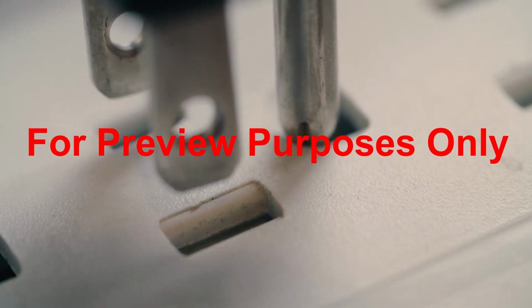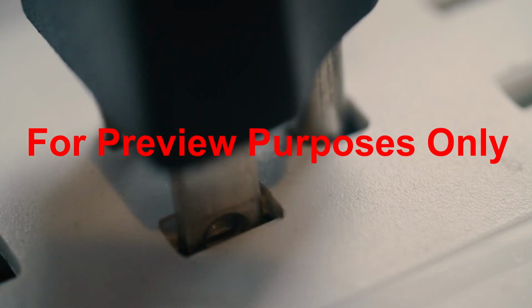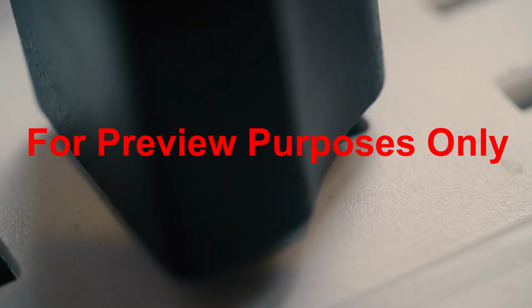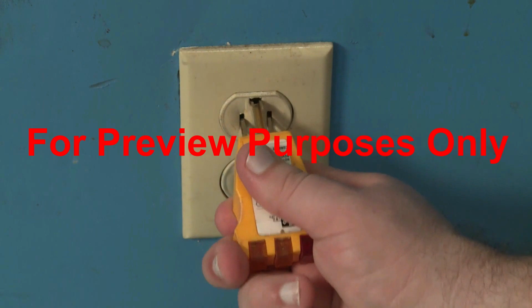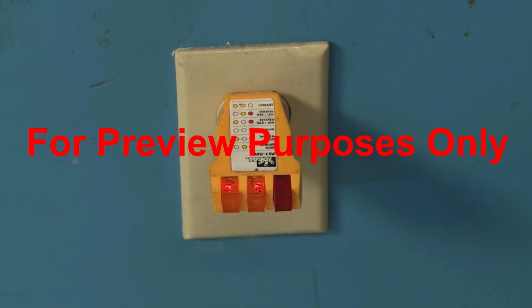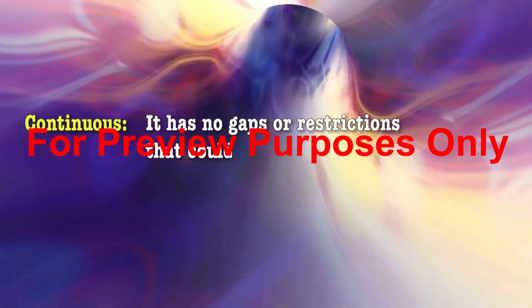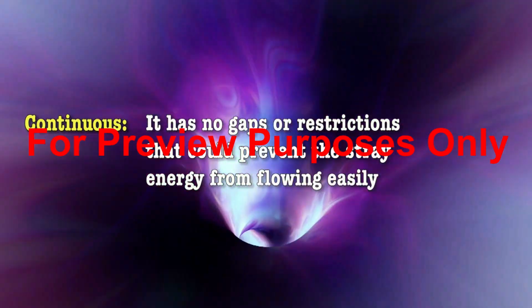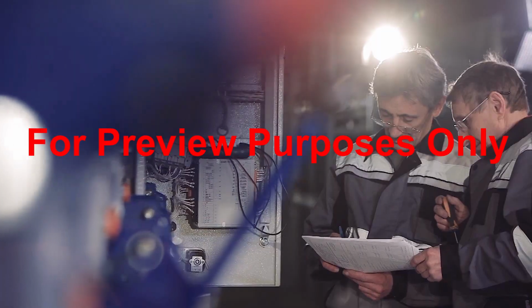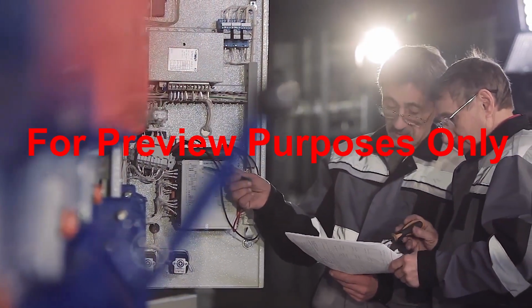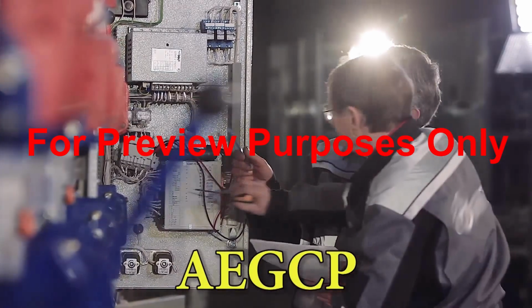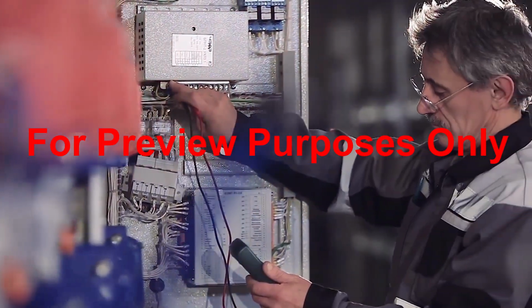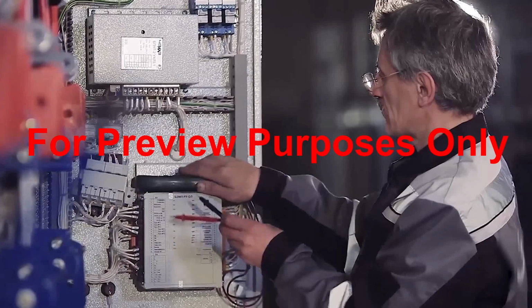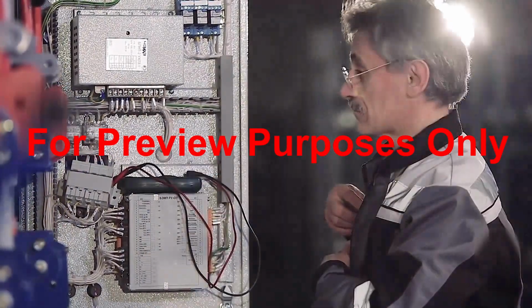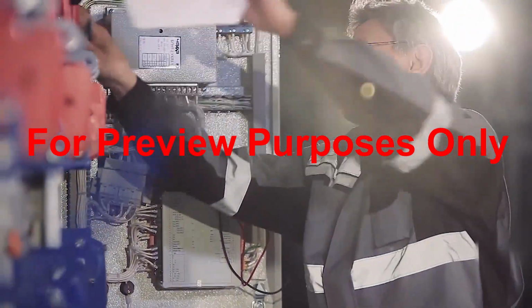If problems cause any electricity to leak in equipment that is grounded, it should jump to this internal ground. But to make sure that this happens, the internal ground connection has to be continuous. Continuous means it has no gaps or restrictions that could prevent the stray energy from flowing easily all the way to the earth. This is where the Assured Equipment Grounding Conductor Program, or AEGCP, comes in. An employer that chooses this option must create and implement a program to ensure that the ground connections on each of their job sites are continuous.